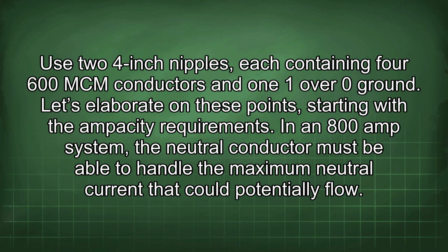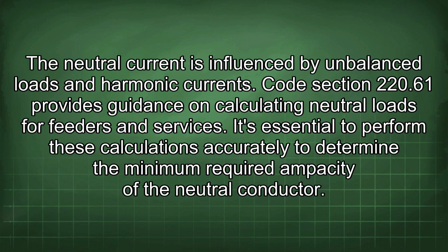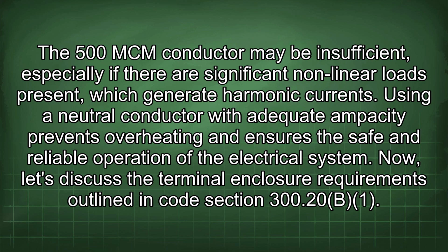Let's elaborate on these points, starting with the ampacity requirements. In an 800 amp system, the neutral conductor must be able to handle the maximum neutral current that could potentially flow. The neutral current is influenced by unbalanced loads and harmonic currents. Code section 220.61 provides guidance on calculating neutral loads for feeders and services. It's essential to perform these calculations accurately to determine the minimum required ampacity of the neutral conductor. The 500 MCM conductor may be insufficient, especially if there are significant nonlinear loads present, which generate harmonic currents. Using a neutral conductor with adequate ampacity prevents overheating and ensures the safe and reliable operation of the electrical system.